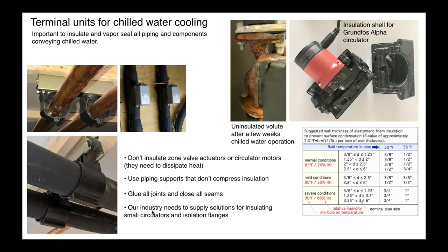And, you know, again, we've talked about this. I want to stress, if we've got some circulator manufacturers looking at the webinar today, guys, we need some products that do chill water in small circulators. We need circulators compatible with those low water temperatures, and we need to have some kind of a good solution for insulating those volutes. We're going to see more applications, whether it's in the air-to-water heat pump market or the geo water-to-water market, where those circulators are going to be in conditions that will produce this kind of surface corrosion. So we need a good solution. So that's my plea to the circulator manufacturers today.